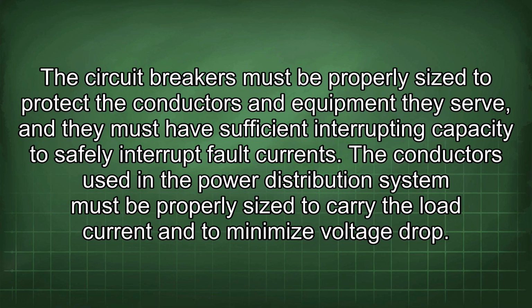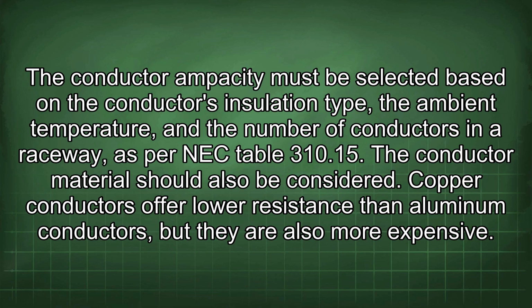The conductors used in the power distribution system must be properly sized to carry the load current and to minimize voltage drop. The conductor ampacity must be selected based on the conductor's insulation type, the ambient temperature, and the number of conductors in a raceway, as per NEC Table 310.15.